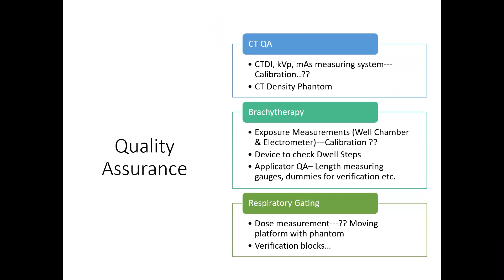And certainly you need QA devices for your daily quality assurance. At the start of every day, you need to check the output of your LINAC. You need to decide whether to buy wired devices or wireless devices. Nowadays, a lot of beautiful wireless devices are available. I remember 20 years back when I started my career, we were putting wires into our Cobalt 60 unit and linear accelerator bunker, and every day it was taking us around 30 minutes on one machine. So nowadays these wireless devices are very beautiful. It just takes 5 to 10 minutes to get your output checked.